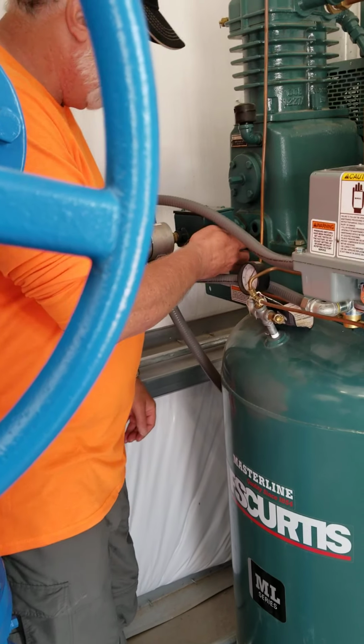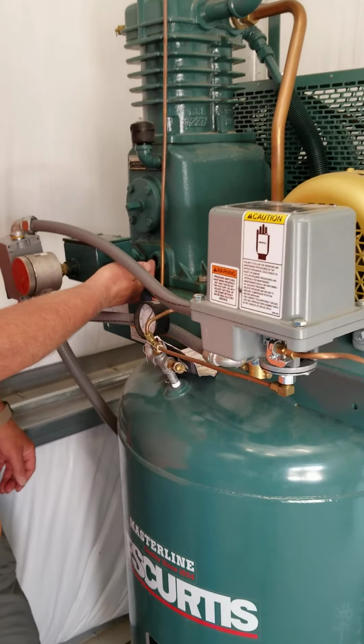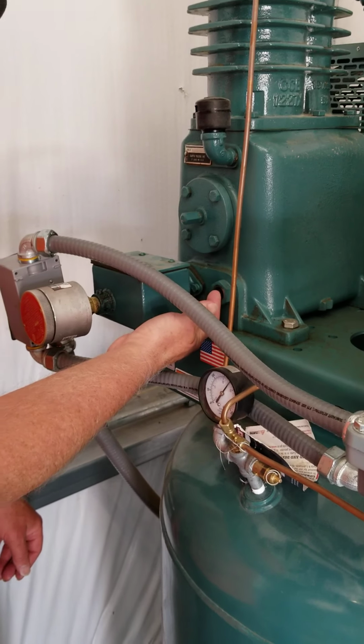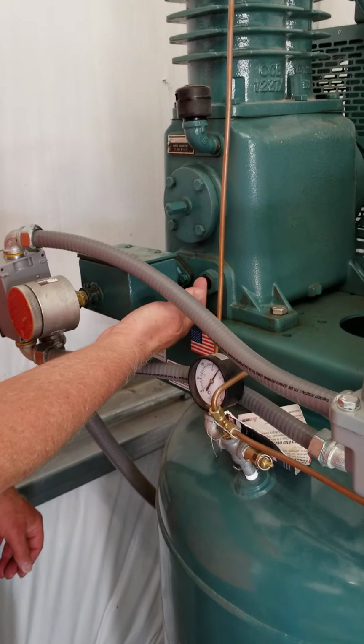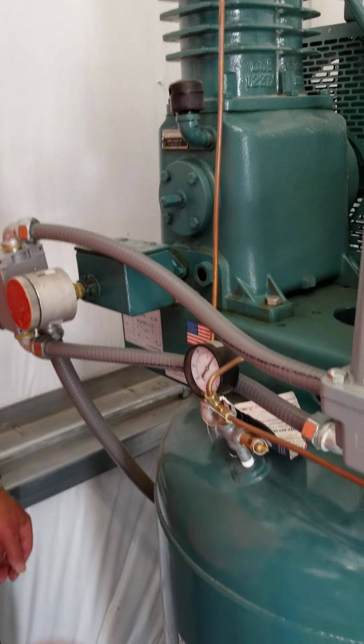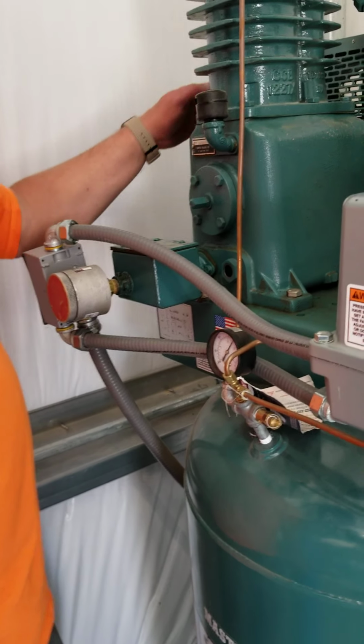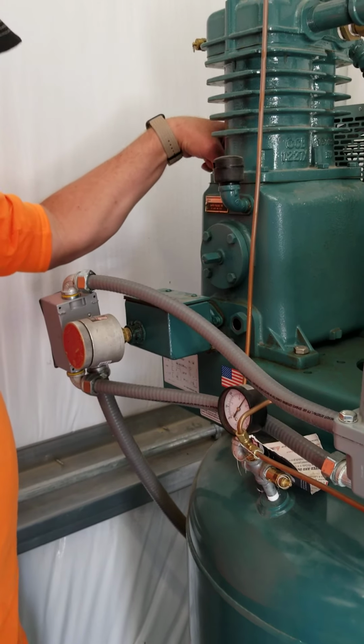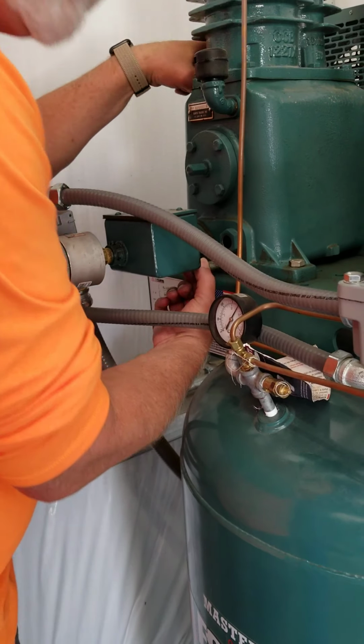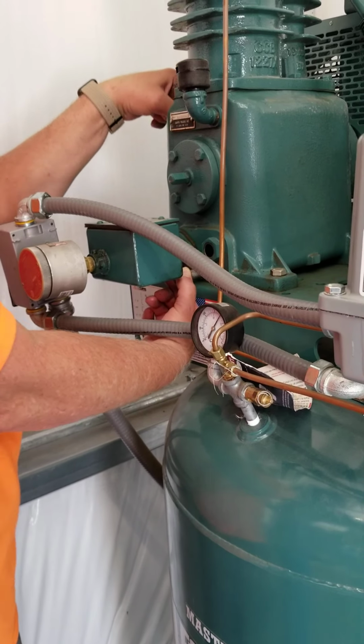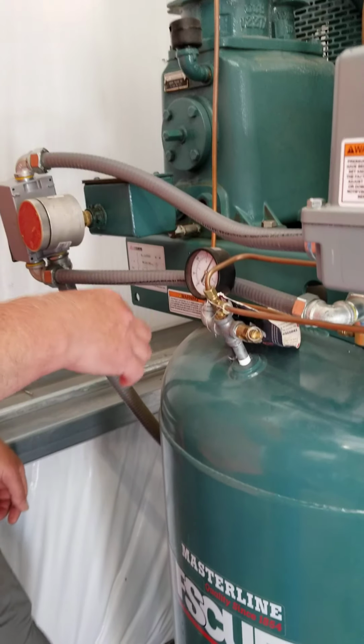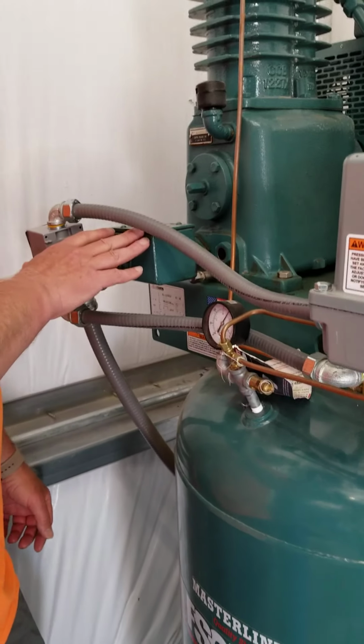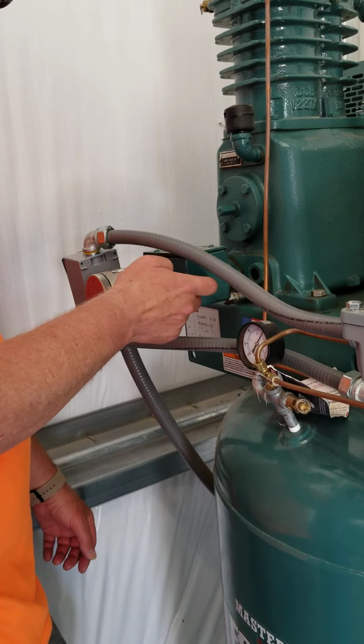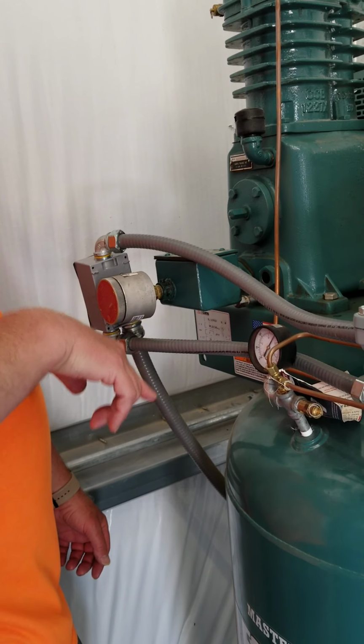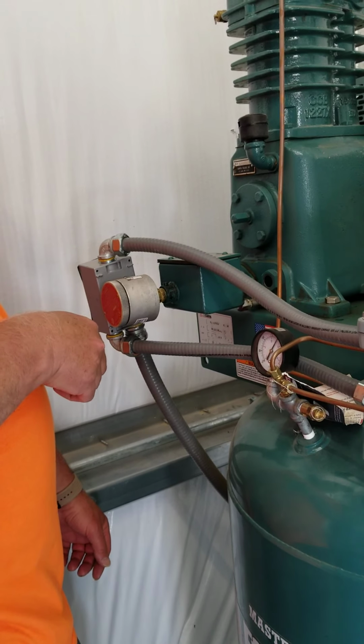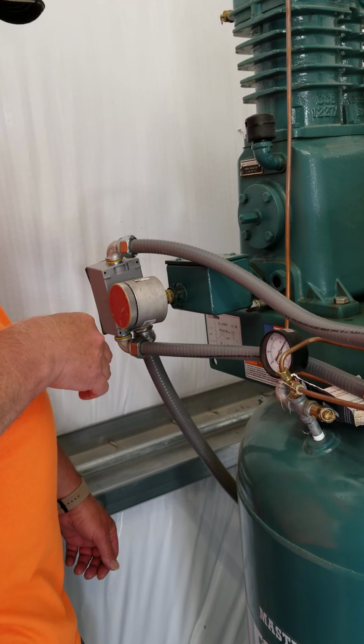You have an oil level gauge here. The oil level, it's hard to see here because it's darker, but it's going to be up near the top, just below the top of this glass. You have a fill cap that's red on this other side, and then your drain tube is here for draining the oil to replace it. You do have a low oil level switch. If the oil level goes low, there's a float in this box that will drop down, and it will kick off your air compressor and give you an alarm that the oil level is low.